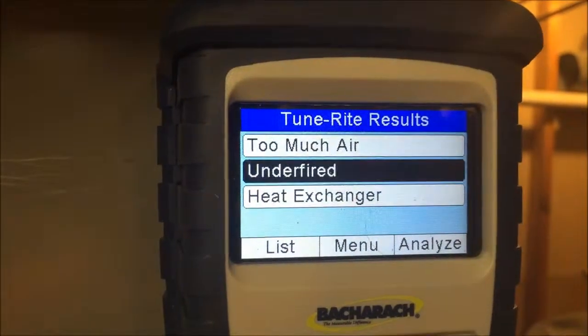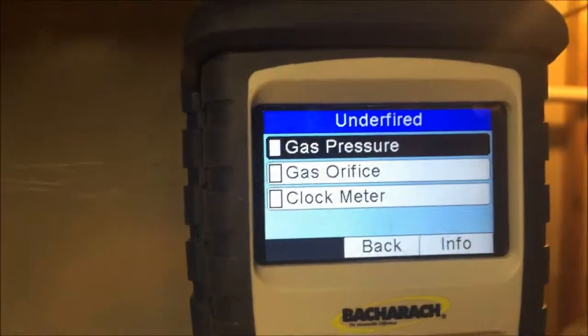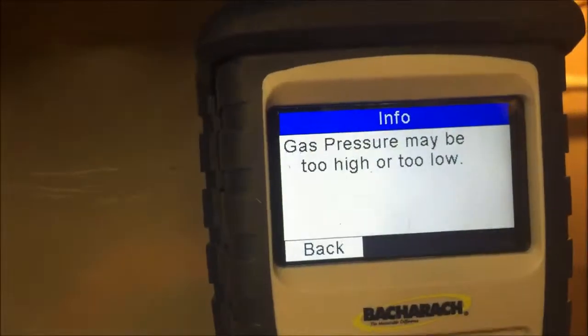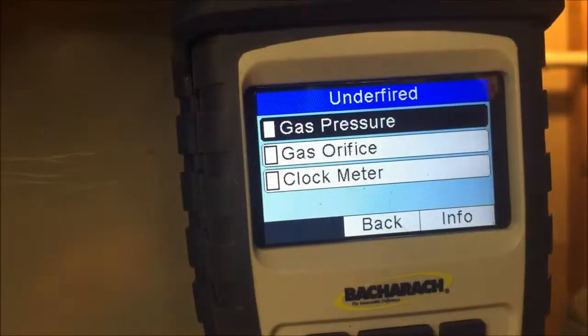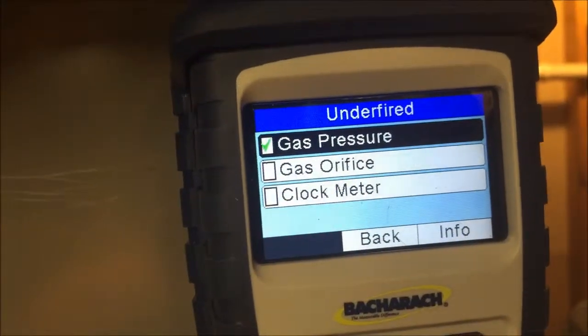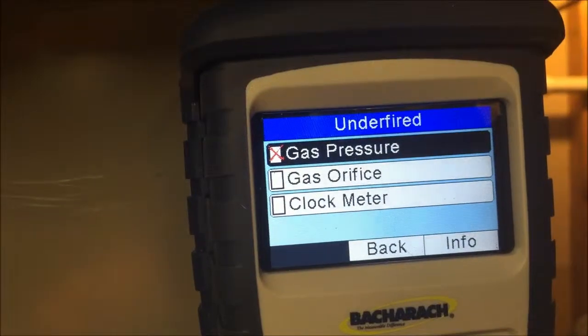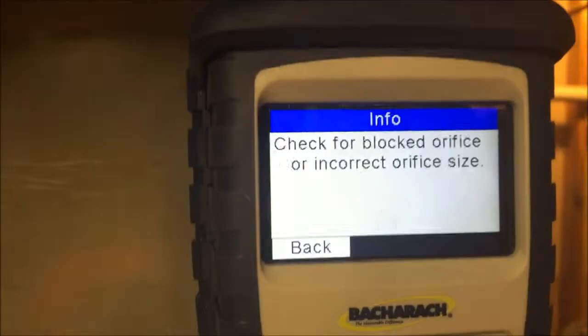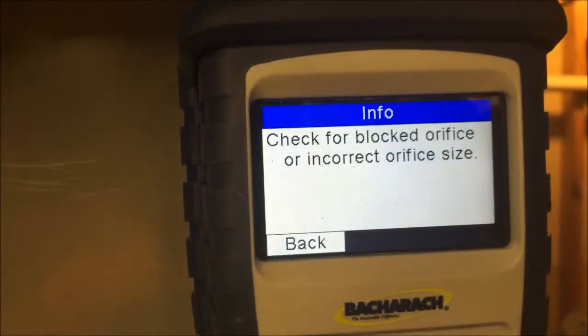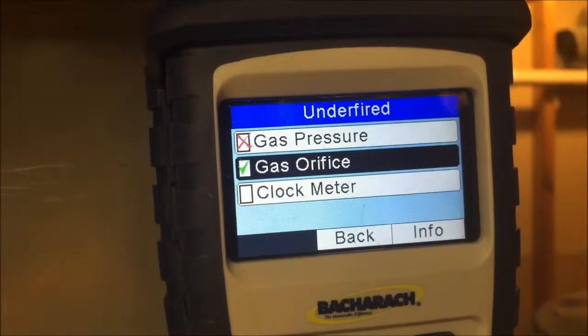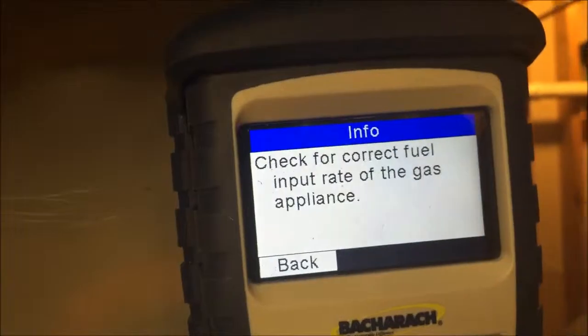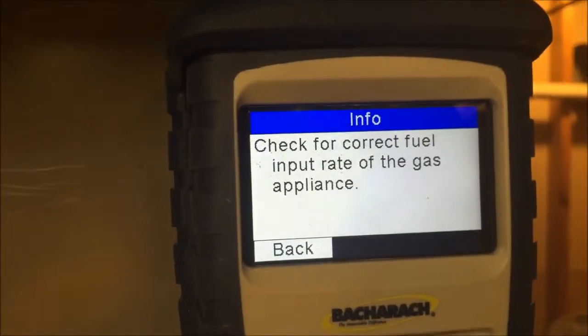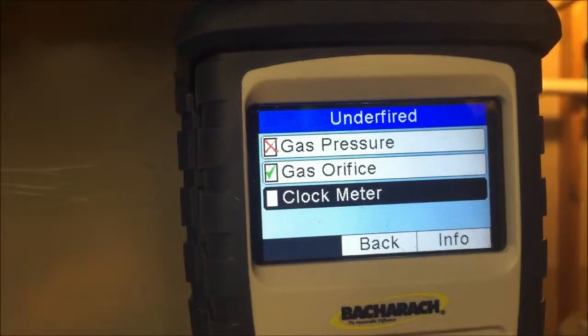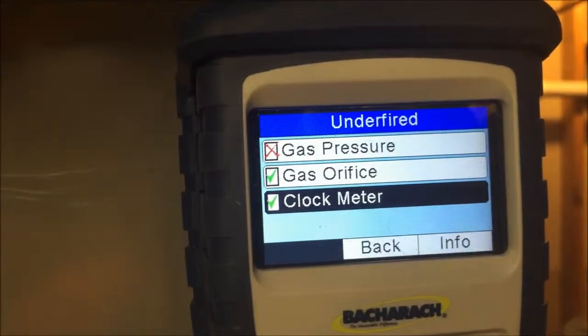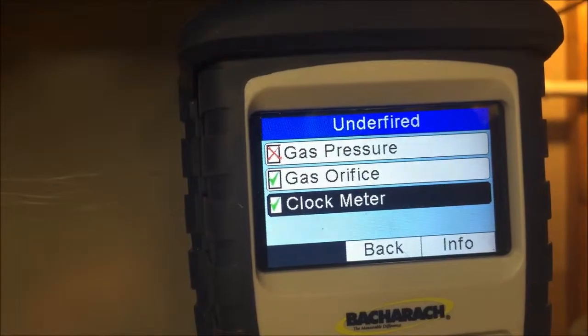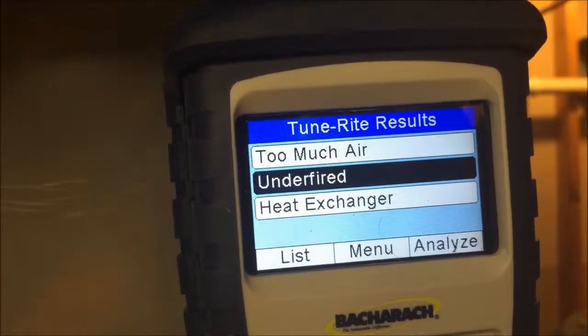So let's check out underfired. This is the other one. Gas pressure may be too high or too low. Let's say that was also the case. Let's say we were also a little off on that as well. Gas orifice. Check for the blocked orifice or incorrect size. We know that's the correct size. And clock the meter. Check for correct fuel input rate. Okay, it was clocked when it was installed. It was done proper, so it's back. So right now we've changed the gas pressure, and we did test at low fire first time, so it's two things we've done.